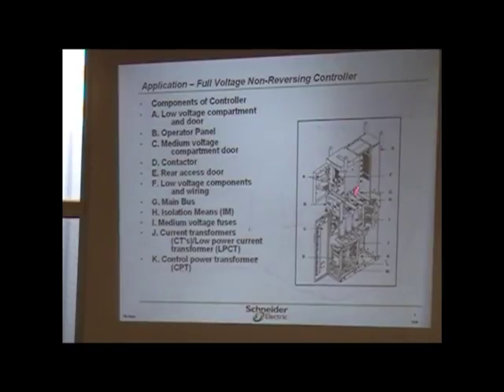If you're trying to troubleshoot and find out why something doesn't close, you can actually pull this contactor out of there and troubleshoot it outside of the cell itself. And the thing we have to remember is you can troubleshoot this by just having control power to the system, with it disconnected completely, isolated and stuff like that.